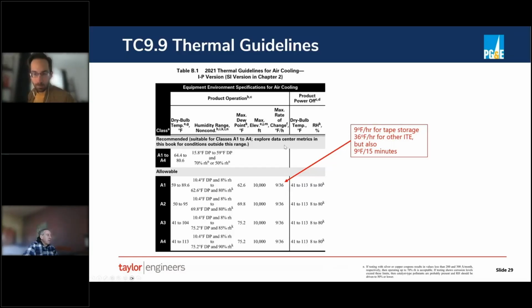And you don't want to be swinging too dramatically, according to this. And here's the range. You can swing 9 degrees per hour if you have tape storage, which almost nobody does anymore. That's a pretty antiquated technology at this point. And you can have much more dramatic swings, if you will, 36 degrees in an hour for basically everything else. But then there's also a 9 limit in the shorter time scale.